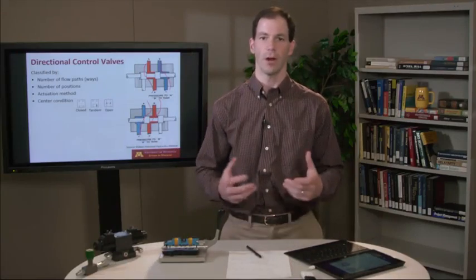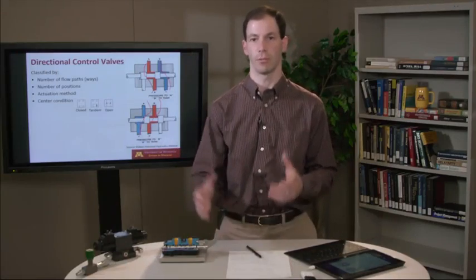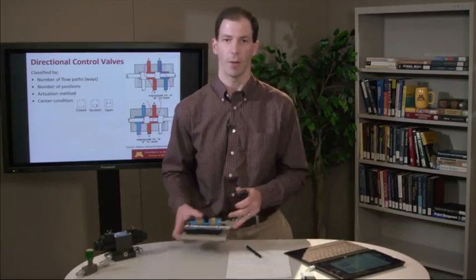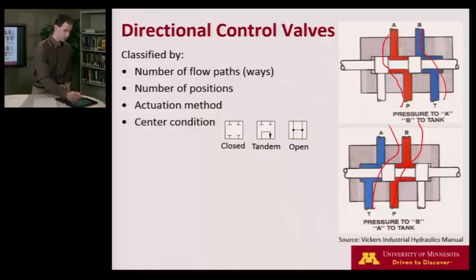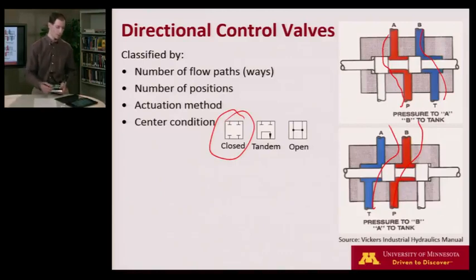The last main one is the center condition. This refers to what happens when I do not have the valve shifted. When it's just in its center condition, am I having a closed port, which is what's sketched right here where all four ports are blocked? Do I have a tandem operation where the pressure would be connected to the tank? Or do I have an open configuration where the A, B, pressure and tank are all connected? Those would be the center conditions.